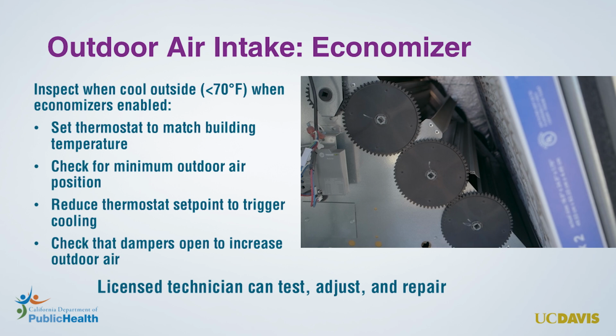This must be done when it's cool outside, below about 70 degrees Fahrenheit. First, set the thermostat set point to match the current temperature indoors so that the thermostat is not calling for cooling. Next, inspect your economizer and check if the dampers are partway open to the outside at a fixed position.